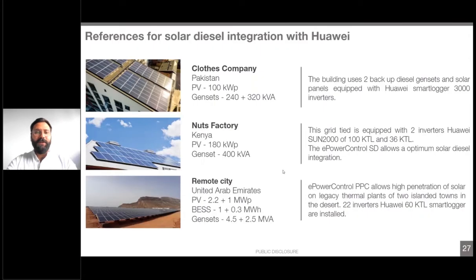Finally, some references. Here are some small references with Huawei inverters. The first project was for a company in Pakistan. We were able to use our solar diesel controller, or hybrid fuel saver, to integrate two different gensets, and by that provide, as I said, zero export when the grid is available and minimum genset loading once there is a switch to the backup genset. We used the Huawei Smart Logger for this project.